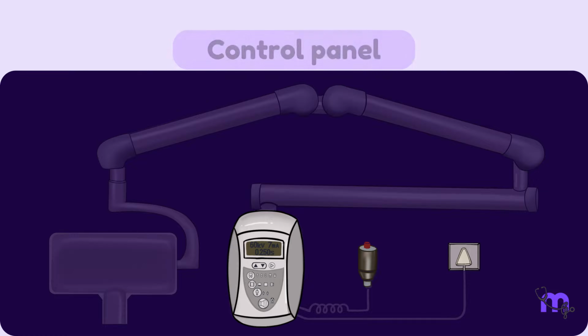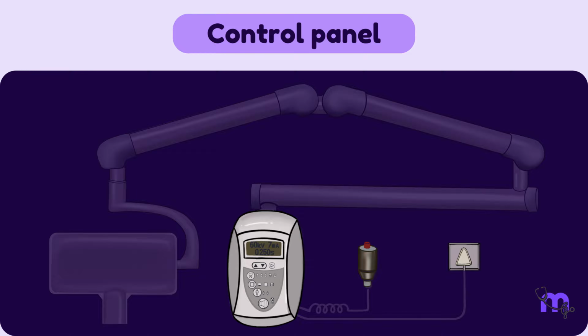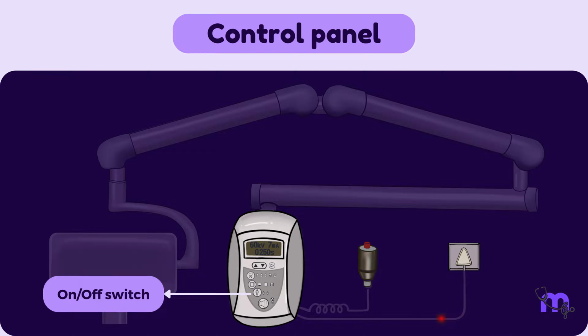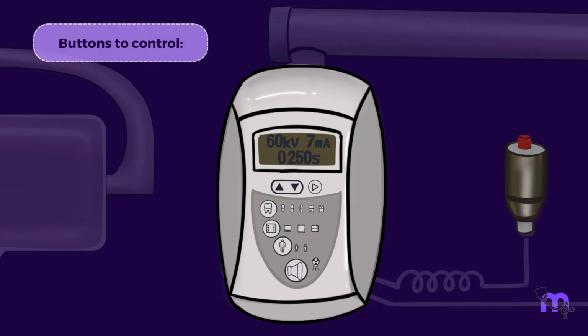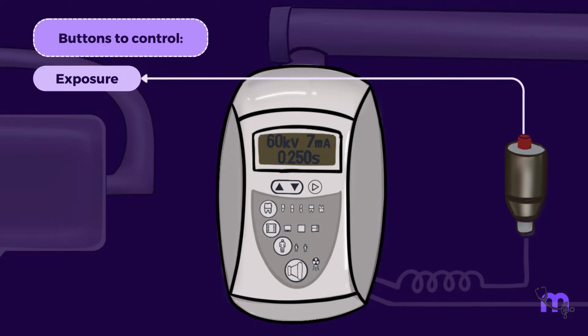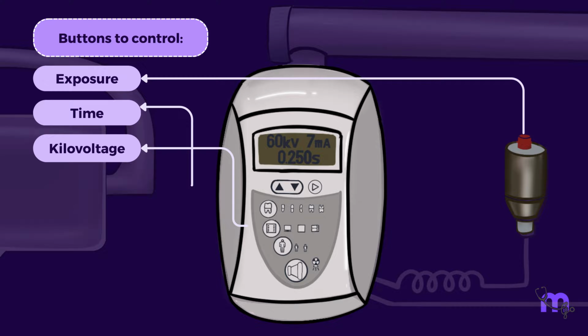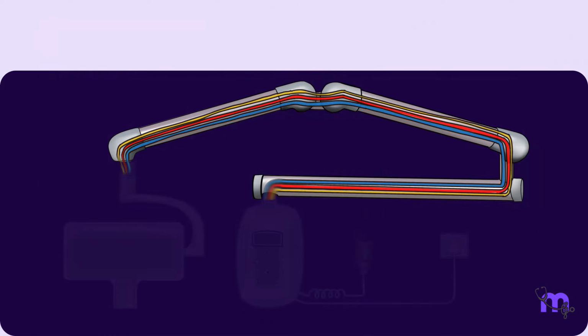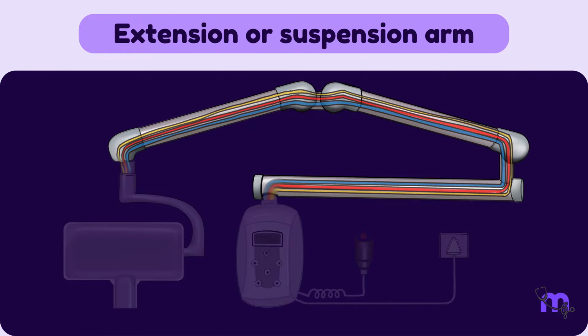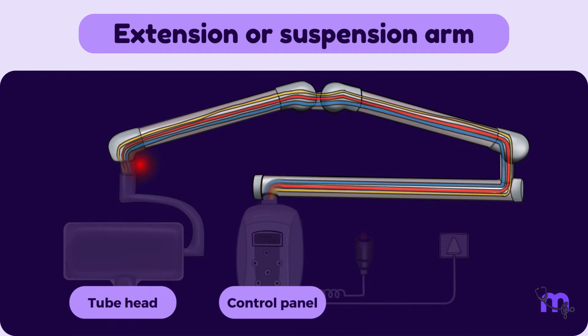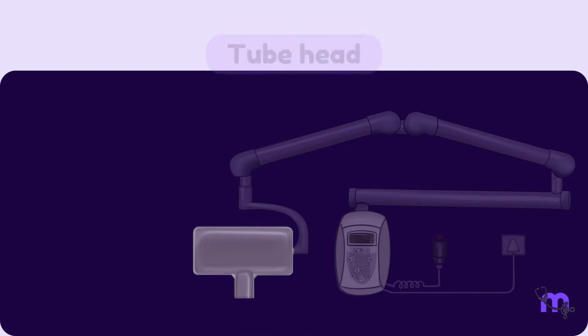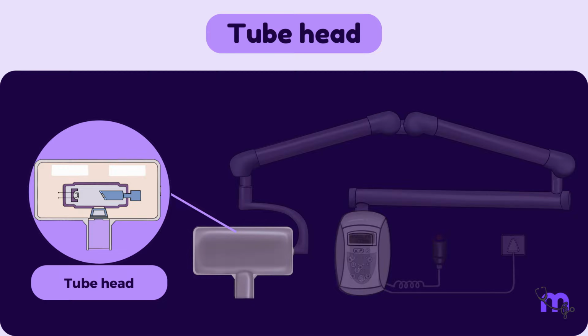Let us first discuss the control panel. It is controlled by the on and off switch and is plugged to an electrical outlet. It also has buttons to control the exposure, time, kilovoltage, and milliamperage that help regulate the X-ray beam. Next, we have the extension arm, also called the suspension arm, that suspends the X-ray tube head and houses all the electrical wires that extend from the control panel to the tube head. The third part is the tube head itself, which has different parts that serve different functions. Let us discuss these in depth.